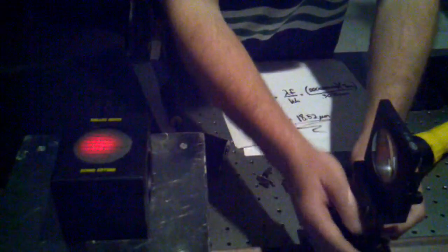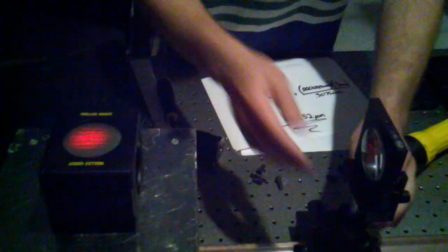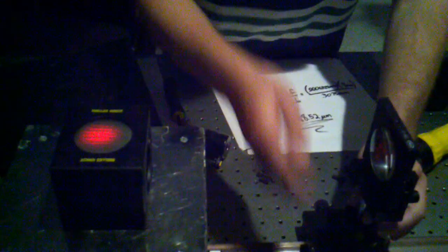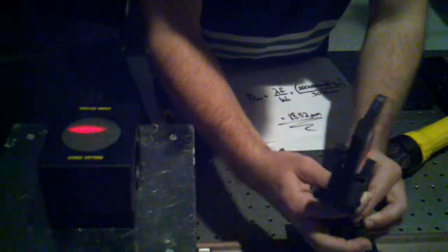For the orientation of our collimating lens, we had the curved side facing away from the microscope in order to minimize spherical aberration. You can see that the lines are pretty much parallel here. And then if we switch the lens around so that the curved side is facing towards the microscope objective, and then we align it again, you can see that the lines are a lot more curvy, which means they have more spherical aberration.